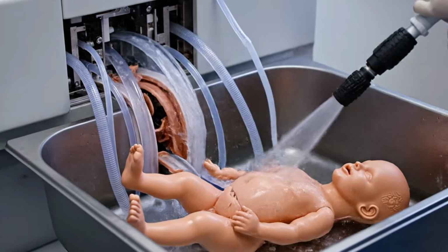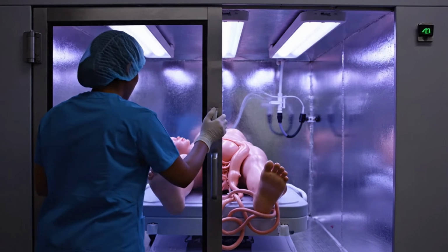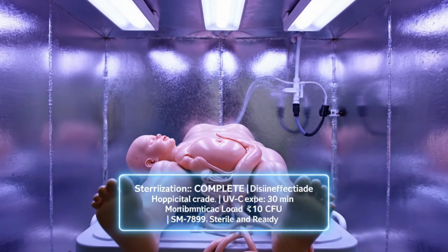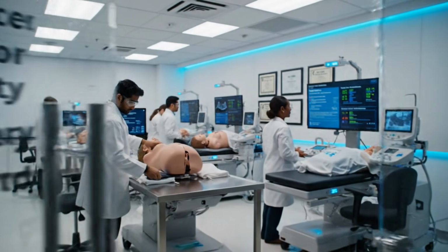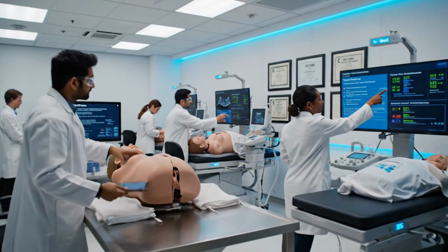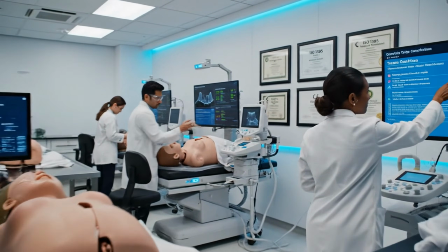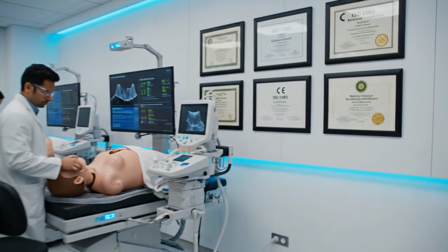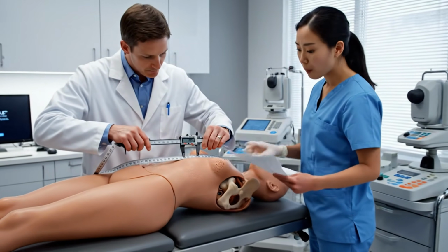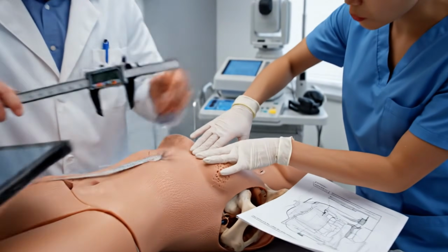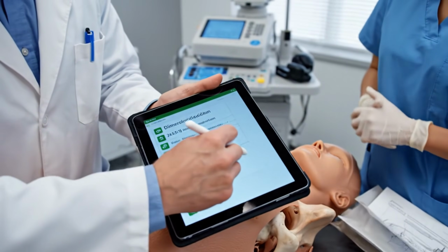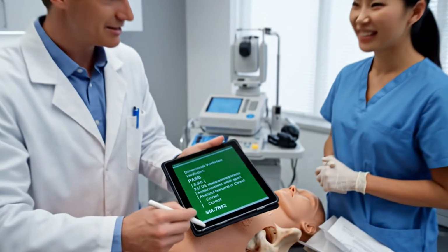The uterine module response is within the specified parameters for scenario 3. How's the sensor calibration? Also verified. Dimensional verification. Pass. 24 out of 24 measurements within spec. Anatomical landmarks. Correct. SM7892.